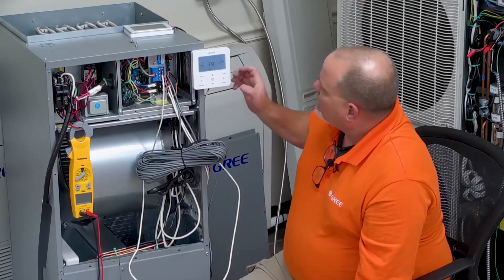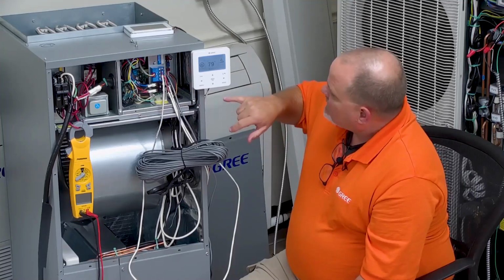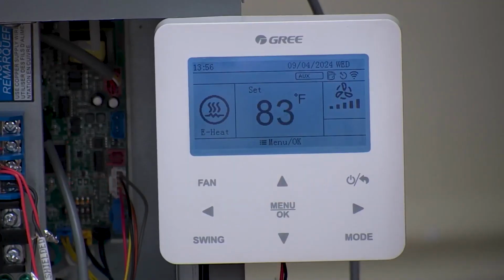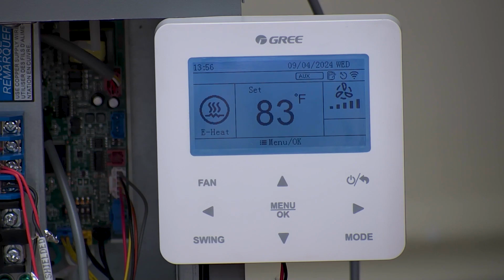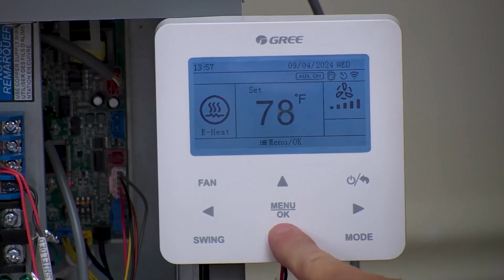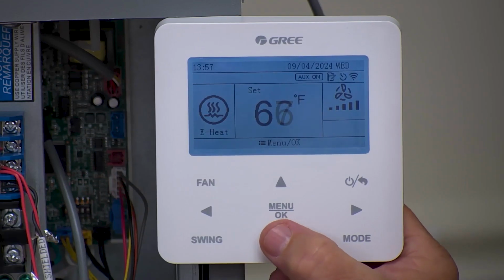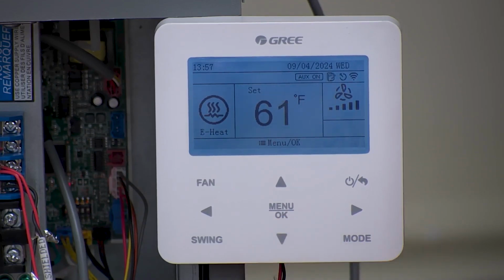So now let me turn it on. So you can see I got eHeat mode. So now I can crank this up, and I should be able to get my electric heat to come on. There it goes. In a minute here, I should see amp draw. There we go. So about 19 amps. We're on 208, so it's going to be 18, 19 amps. Then if I run my temperature down, I should be able to get it to cycle off.